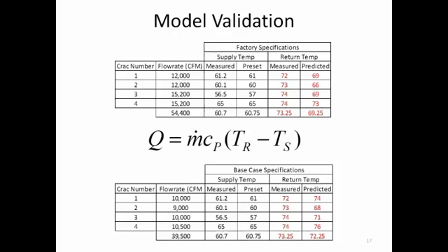The other thing that I think is important to point out is that measurement itself gets problematic. One of the things here, Liz, that I've always noted is we measure the return temp on the CRAC units using whatever the CRAC unit reports. Well, the CRAC unit's reporting a single point on the return. It's a probe. Where here, what we predict is an average based on a surface. That's an average. Yes. Average across the entire CRAC surface. Exactly right. The entire return surface, right? Exactly right. So we don't know what the profile really looks like. We're merely measuring apples and oranges here.